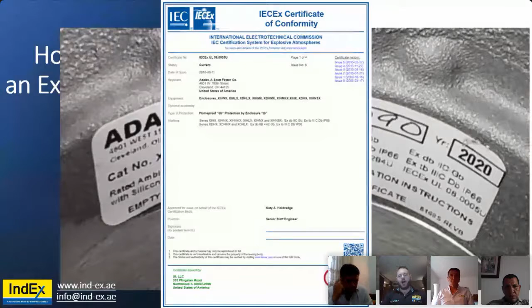Now, IEC brings this all together, bringing that equipment certificate shall be prepared for each installation, but it shall be part of a verification dossier. A verification dossier is like an equipment register. Each individual item will be a row. You could have 300,000 items across site, and each column is a different data set. So this can be kept digitally, which I highly suggest, or a hard copy. It's done in order to correctly install and maintain and ensure the safety of an installation.